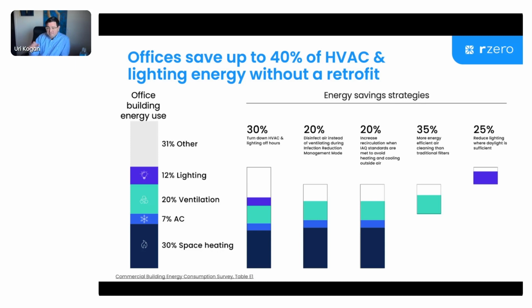The fourth strategy is a bit more conventional because it relies on changing physical equipment, specifically filters. Lots of folks have been paying close attention to filtration in the last few years because many building owners and managers have responded to the pandemic by increasing their filters from MERV 8 to 13 or higher. That often ends up creating an energy penalty because you have to push air harder to get through the filter. But there are actually alternative technologies that can deliver an even higher rate of particulate capture.